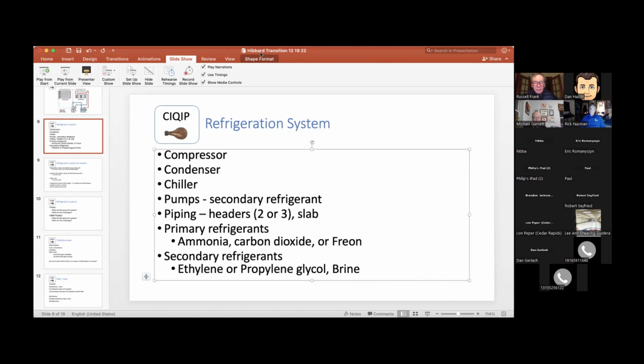What's the difference between having 2 or 3 headers? If you have a 3-sheet club, you'll typically have 2 headers. If you have a 4, 5, 6, or even up to 8-sheet club, you'd have a 3rd header, called the reverse return header. You feed the glycol in at one end and return it from the other end, making a U-turn to bring it back out. So you just have 3 pipes.